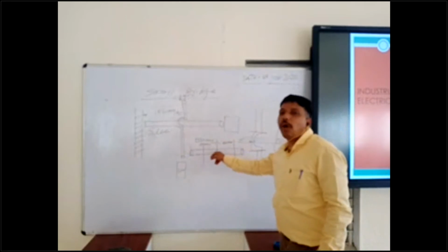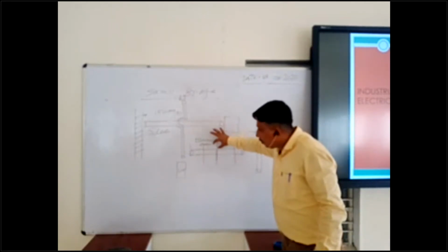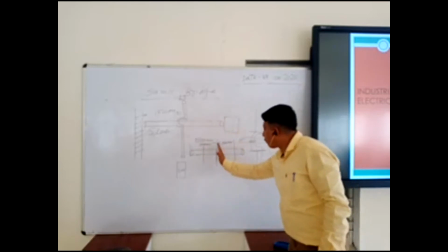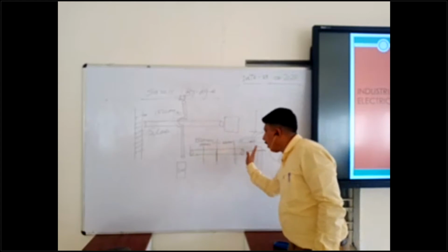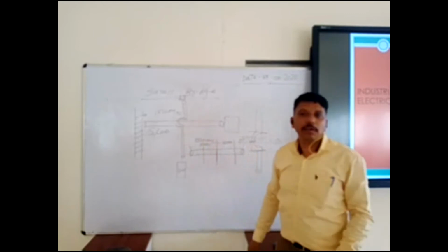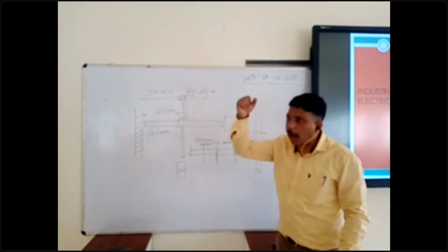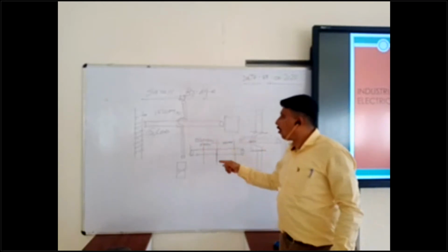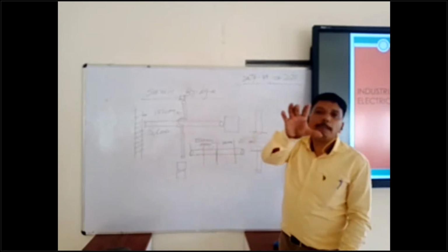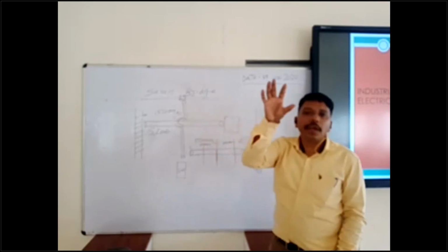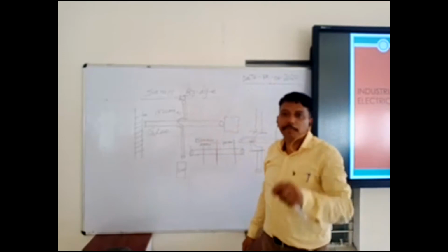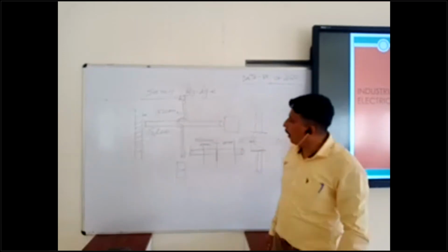The center marking always comes at the crossing pipe, and after this, 10 centimeters or 100 mm on this side and 100 mm from the center point on this side for bending purposes. We can bend with a bending machine, so you can mark like this. If you mark like that, your bent small bridge comes out accurate as per your requirement.